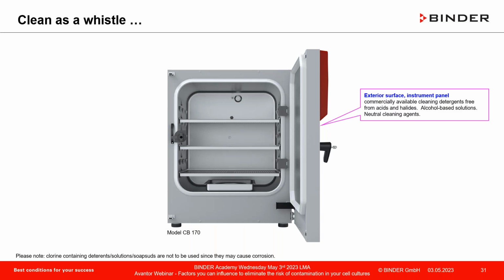All right, exterior surface, instrument panel, regardless if it's a red triangle or anything else, commercially available cleaning detergents free of acids and halogens are fine. Alcohol-based solutions are possible, neutral cleaning agents. So something you will basically find very commonly in cell culture labs. Then you have the silicone door seal or gasket. You can also take them out of the frame and clean them with alcohol-based solutions, because due to the profile, that also might contribute to a risk of contamination.